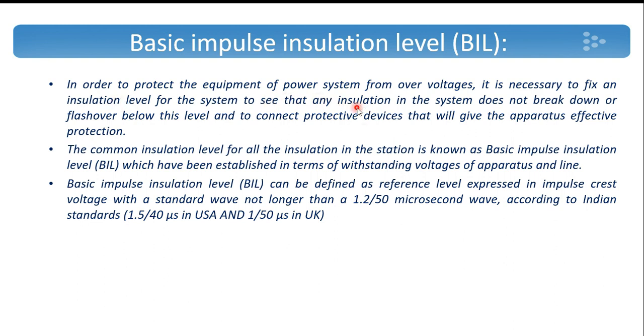Another important term associated with insulation coordination is Basic Impulse Insulation Level (BIL), which is a standard value of insulation level. In order to protect equipment from over-voltages, it is necessary to fix an insulation level for the system so that it should not break under normal working conditions. The common insulation level for all insulation in a substation is called the Basic Impulse Insulation Level, which is established in terms of withstanding voltages of apparatus and lines. BIL is defined as a reference level expressed in impulse crest voltage with a standard wave not longer than a 1.2 by 50 microsecond wave, according to Indian standards.